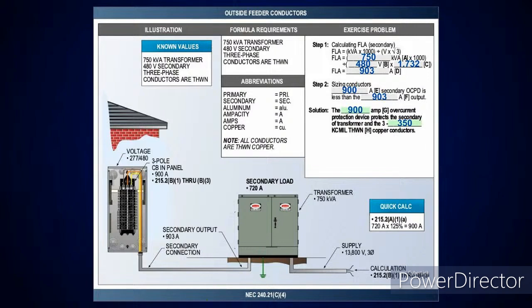Now, remember in this case, and we covered this earlier, 240.4B deals with overcurrent devices 800 amps or less. Once I get over 800 amps, then I'm looking at 240.21C. In this case, my conductors have to be equal to or more than the overcurrent protection device at this point, or the load. So that means I have to be equal to it or drop down. Well, I had a 903 output. I can't exceed it, so I have to drop down to the next standard size, which is 900 amp. And then I'm going to look at what type of conductors I need here. In this case, I'm going to need 350 kcmil conductors, which I'm going to parallel three times, which is going to give you 930 amps. I just know that off the top of my head because I've done it so many times.